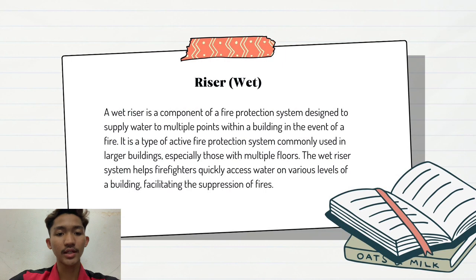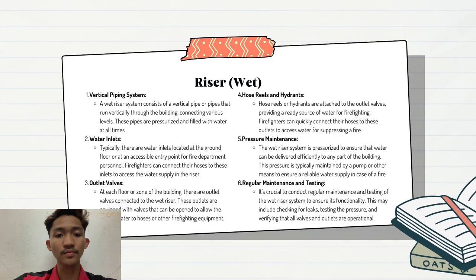Wet riser. A wet riser is a component of a fire protection system designed to supply water to multiple points within a building in the event of a fire. It is a type of active fire protection system commonly used in larger buildings, especially those with multiple floors. The wet riser system helps firefighters quickly access water on various levels of a building, facilitating the suppression of fires. The first component of the wet riser is the vertical piping system. A wet riser system consists of a vertical pipe or pipes that run vertically through the building, connecting various levels. These pipes are pressurized and filled with water at all times.